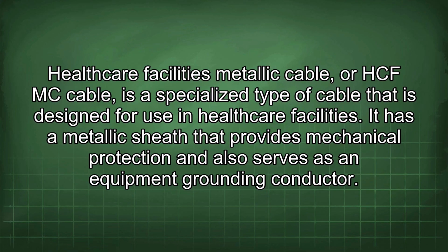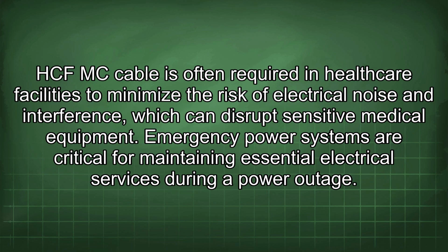Healthcare facilities metallic cable, or HCF-MC cable, is a specialized type of cable that is designed for use in healthcare facilities. It has a metallic sheath that provides mechanical protection and also serves as an equipment grounding conductor. HCF-MC cable is often required in healthcare facilities to minimize the risk of electrical noise and interference, which can disrupt sensitive medical equipment.